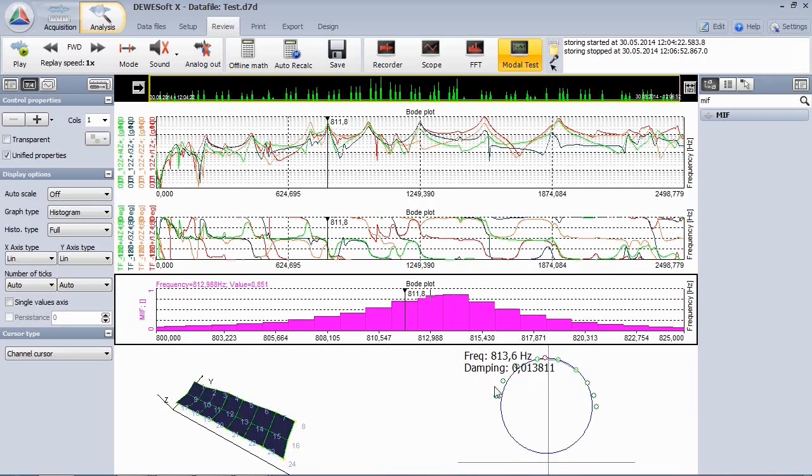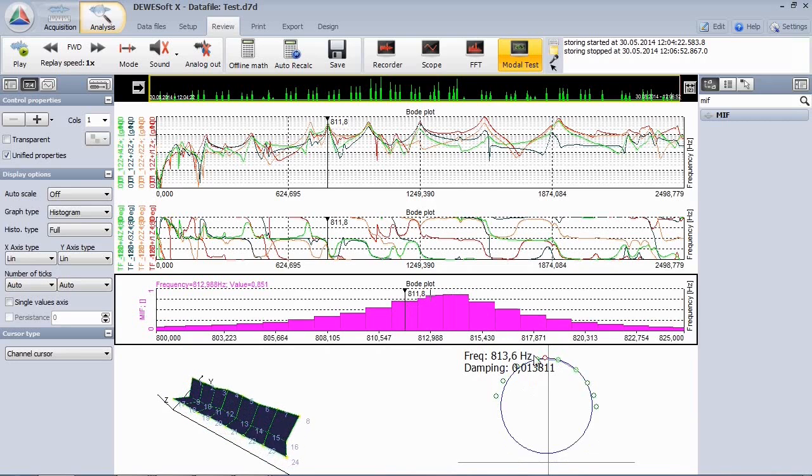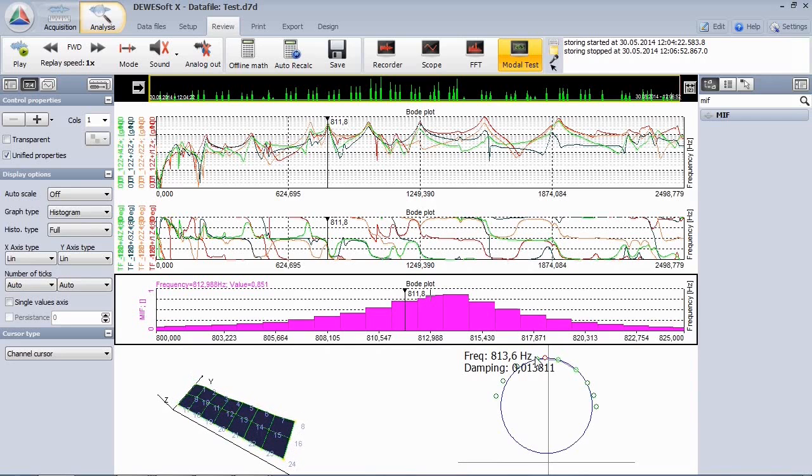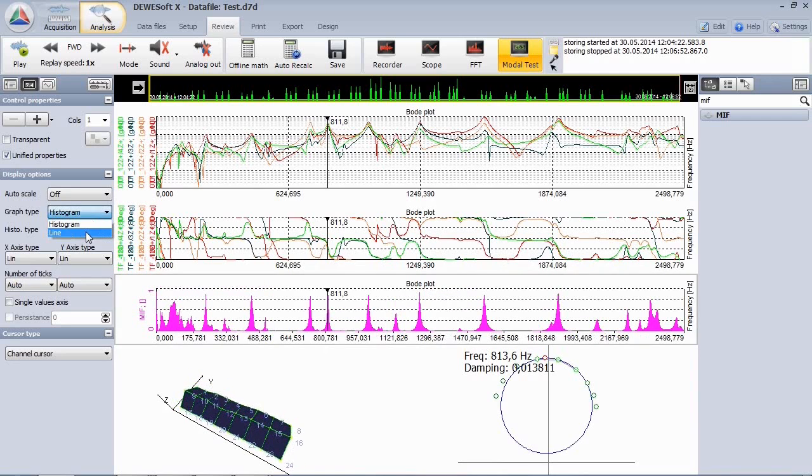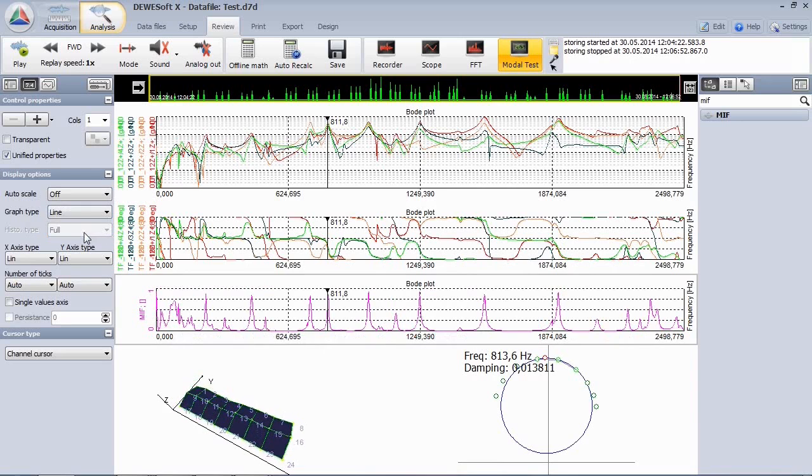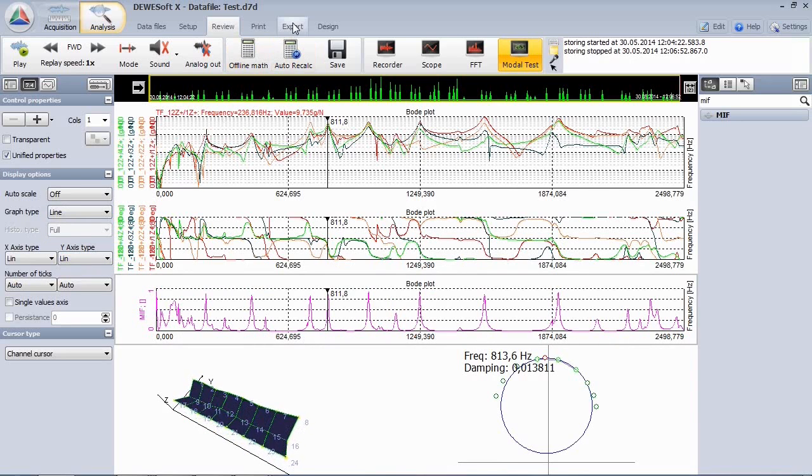Therefore the iterative circle fit method is used. It plots real and imaginary part of the FFT lines around the center peak in the complex coordinate system to determine exact frequency and damping factor.